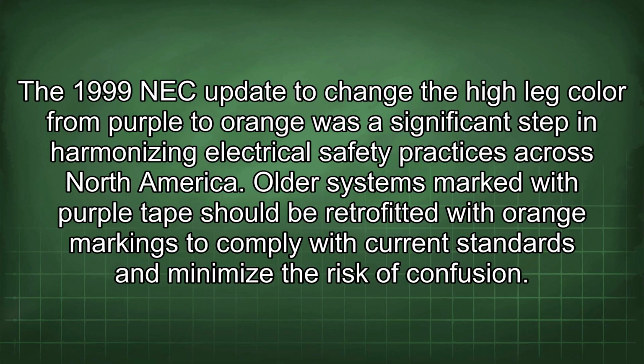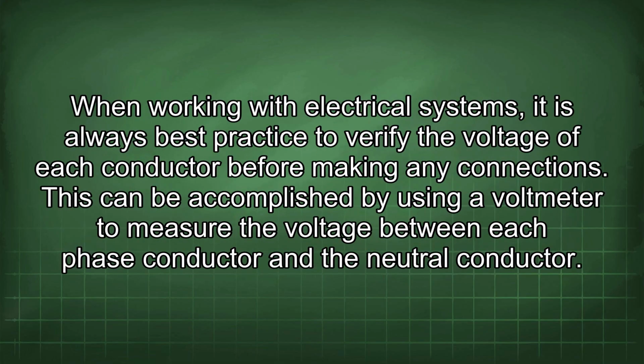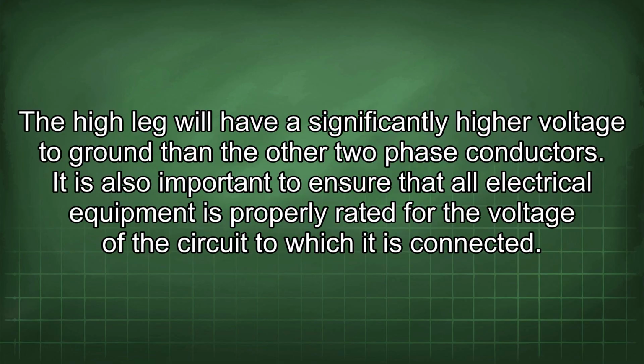The 1999 NEC update to change the high leg color from purple to orange was a significant step in harmonizing electrical safety practices across North America. Older systems marked with purple tape should be retrofitted with orange markings to comply with current standards and minimize the risk of confusion. When working with electrical systems, it is always best practice to verify the voltage of each conductor before making any connections. This can be accomplished by using a voltmeter to measure the voltage between each phase conductor and the neutral conductor. The high leg will have a significantly higher voltage to ground than the other two phase conductors.